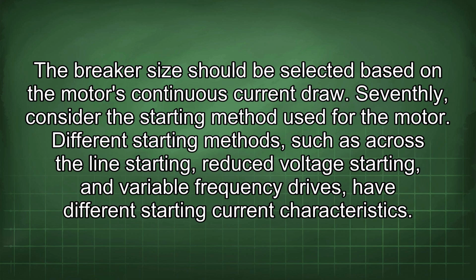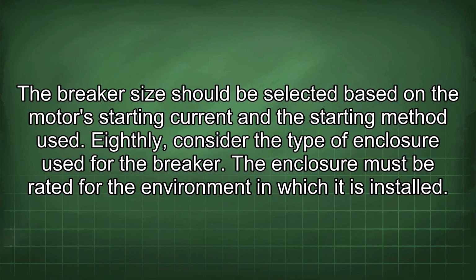Seventhly, consider the starting method used for the motor. Different starting methods, such as across-the-line starting, reduced voltage starting, and variable frequency drives, have different starting current characteristics. The breaker size should be selected based on the motor's starting current and the starting method used.